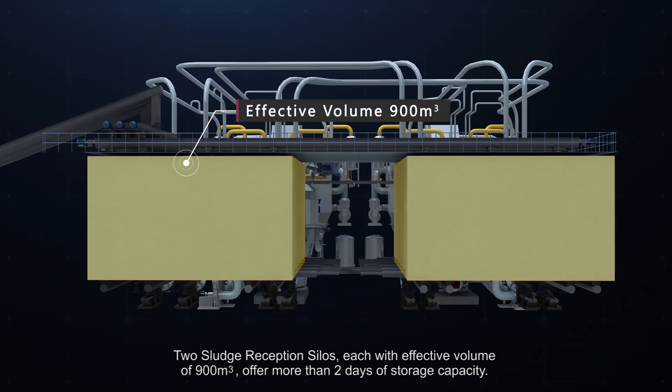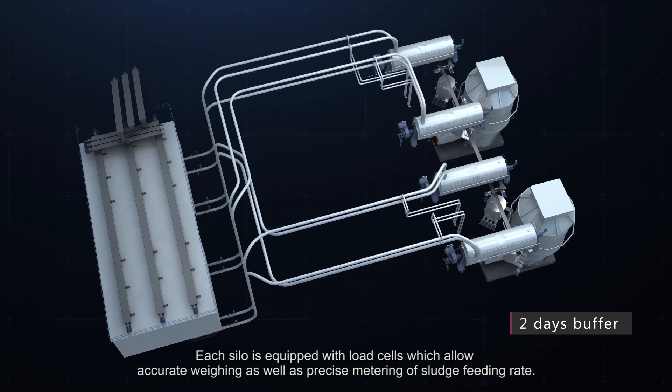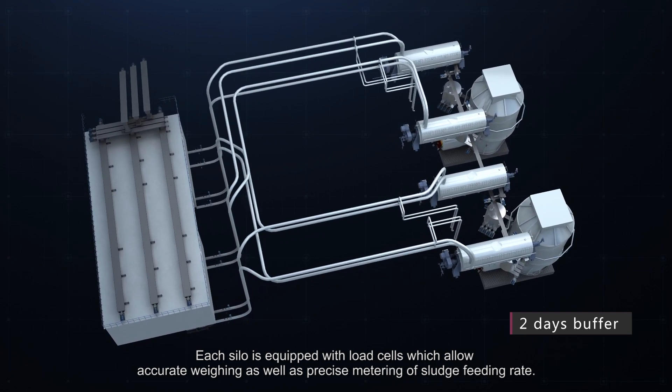Two sludge reception silos, each with effective volume of 900 cubic meters, offers more than two days of storage capacity. Each silo is equipped with load cells which allow accurate weighing as well as precise metering of sludge feeding rate.